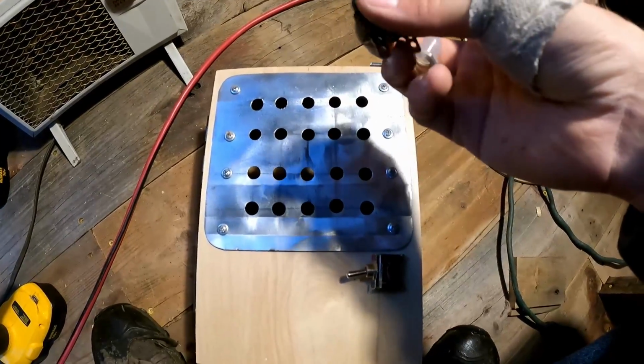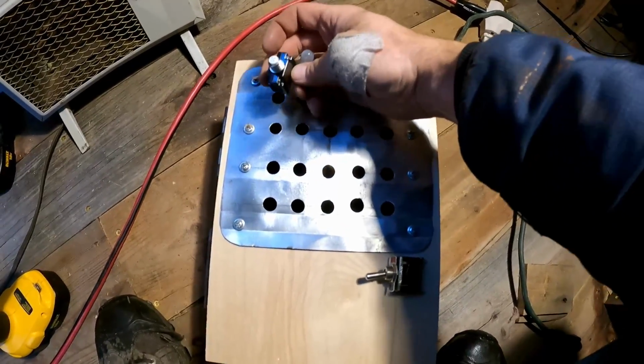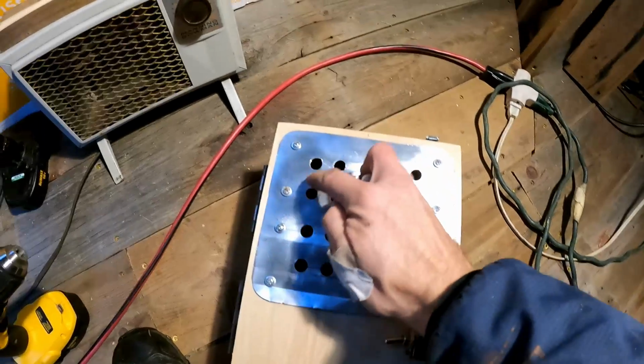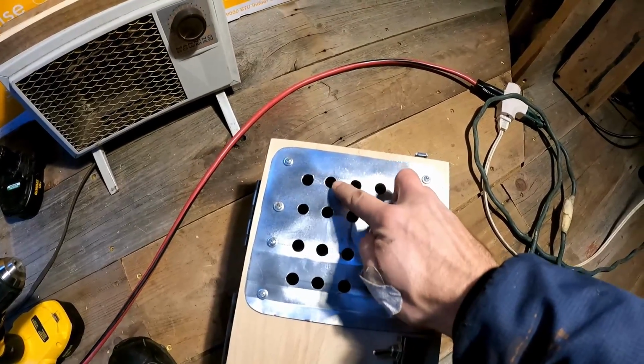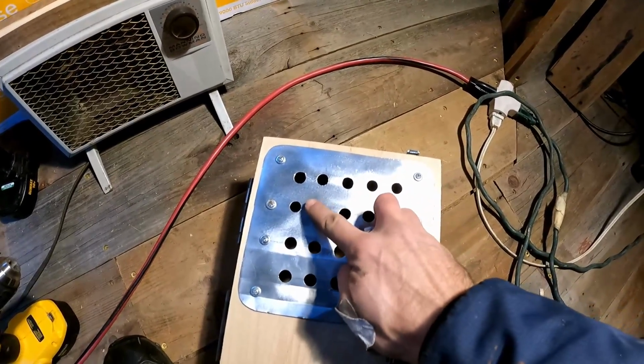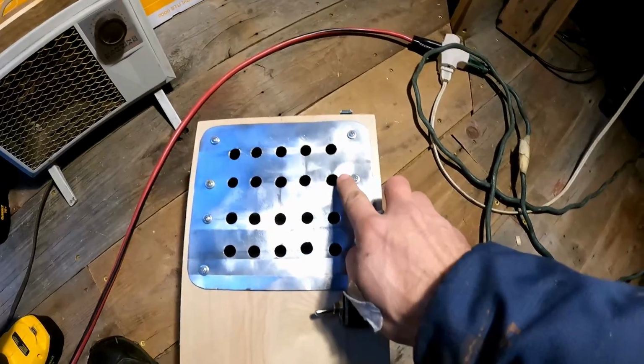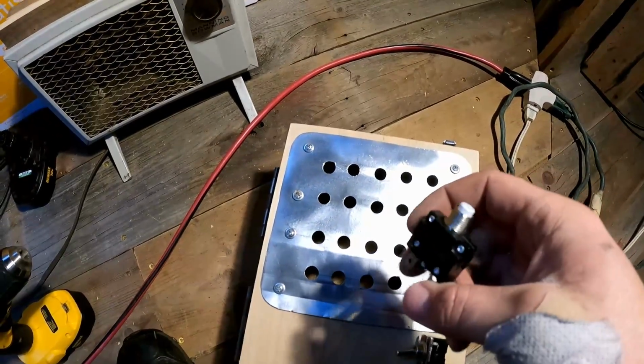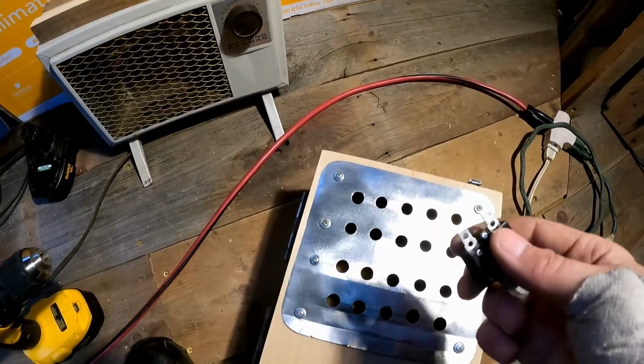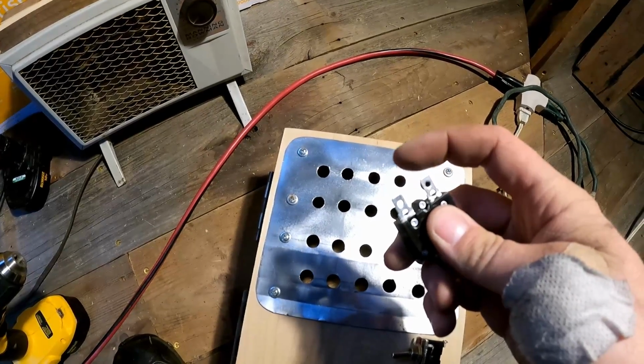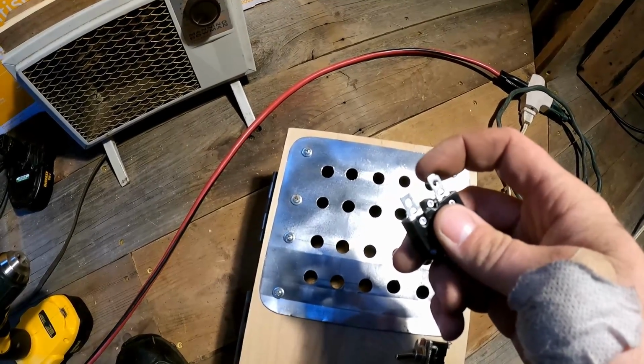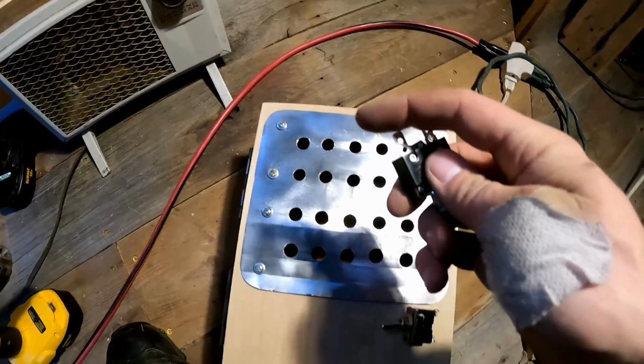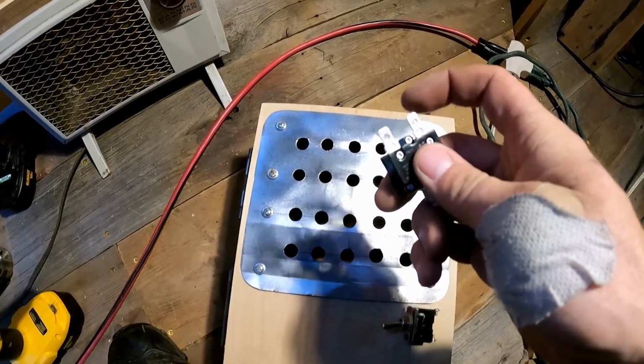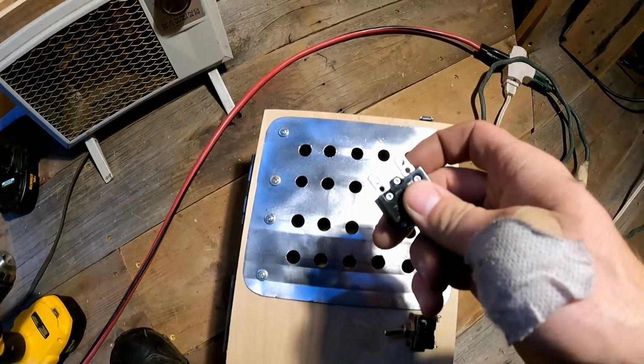I'm going to wire a bunch of these in series with switches. So on the front you just see rows of breaker, switch, top, bottom. There'll be a row of breakers all across, and then a row of switches all across these guys. Behind, I'll wire one set of these terminals all to the same input wire, then jumper from a breaker to a switch and run the output to an actual device.